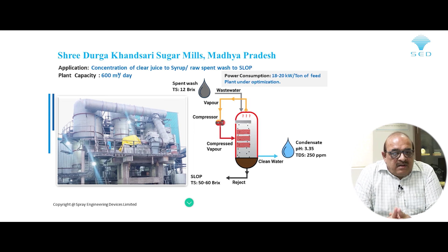Now these two installations on spent wash are already there. After this 600 cubic meter per day plant, the road is very clear for us to go for higher capacity also. Now I have taken two different combinations where we can use the low temperature evaporator. Now the third system where it can be utilized, I will discuss that part. That is regarding cooling tower blowdowns, DM water rejects, CPU rejects, where we want to do the water recovery.